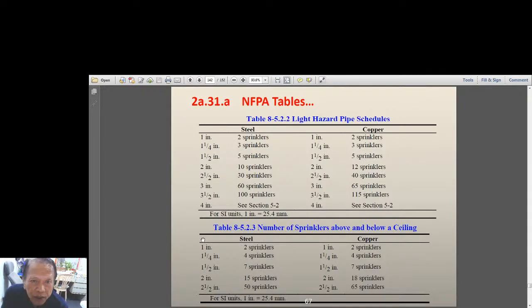Okay, so here the difference between the light hazard is in the number of sprinklers that a certain size of pipe can supply. So for example, for a 2-inch pipe, up to 10 sprinklers. For a 3-inch pipe, up to 60 sprinklers. Okay, so take note, 2-inch, 10 sprinklers, and then 3-inch, 60.